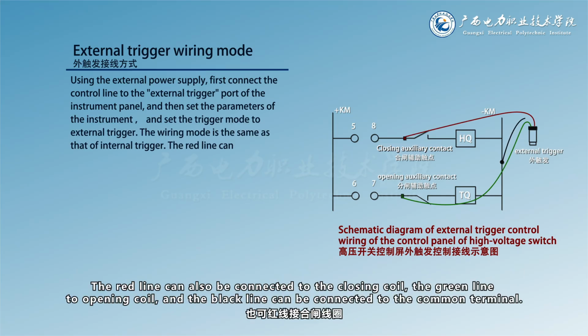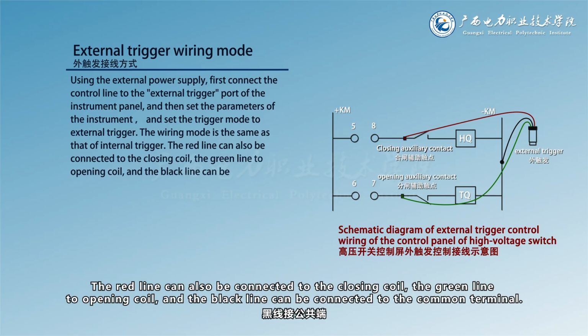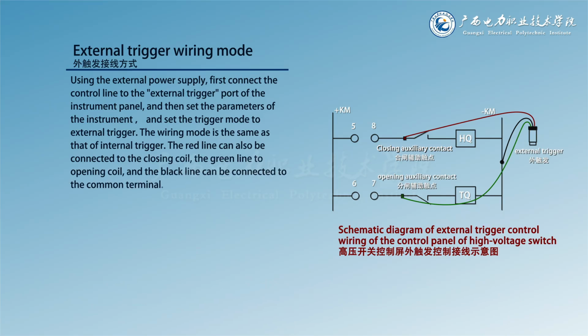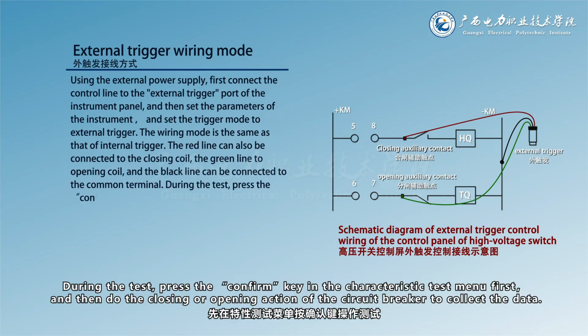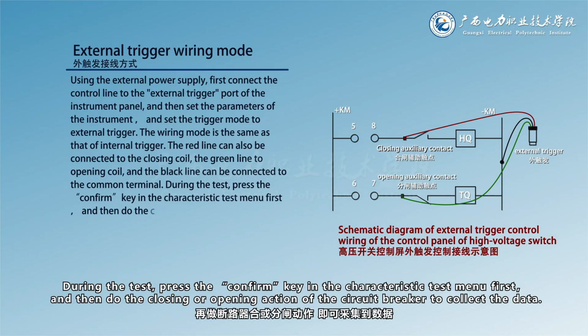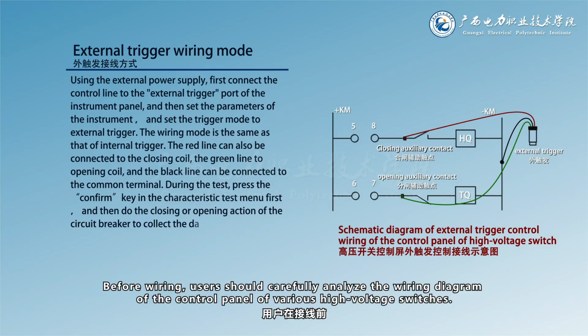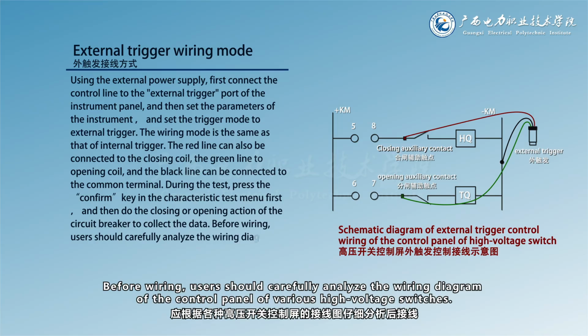The red line can also be connected to the closing coil, the green line to the opening coil, and the black line can be connected to the common terminal. During the test, press the confirm key in the characteristic test menu first and then do the closing or opening action of the circuit breaker to collect the data. Before wiring, users should carefully analyze the wiring diagram of the control panel of various high-voltage switches.